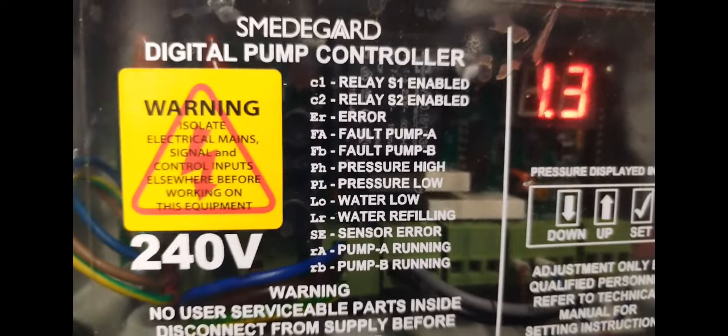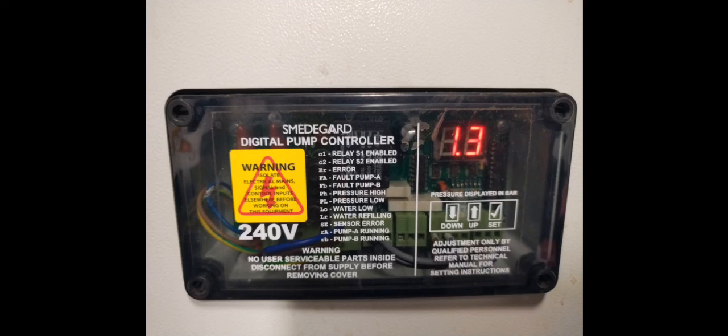And then 1.3 bar on this side of the plate. So there was a plate to plate heat exchanger, and on one side we had 1.3 bar. When we found it, it was about 0.7 or 0.8 bar, but that was adequate. And then the other side, I think it was about 7 bar of pressure on the other side of the plate heat exchanger with the other pressurization unit. So I just went into the bottom of the dosing pot in order to top that system up.